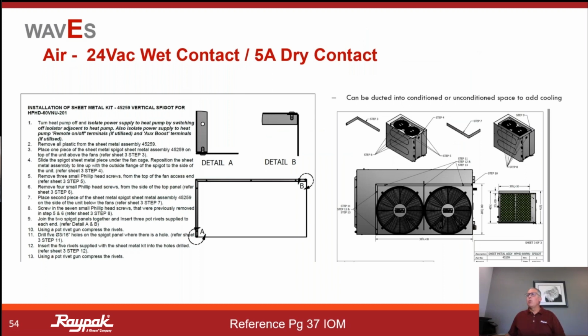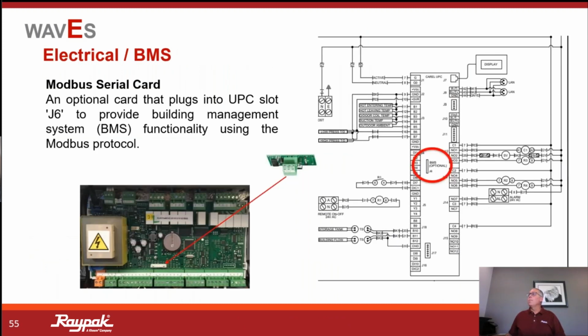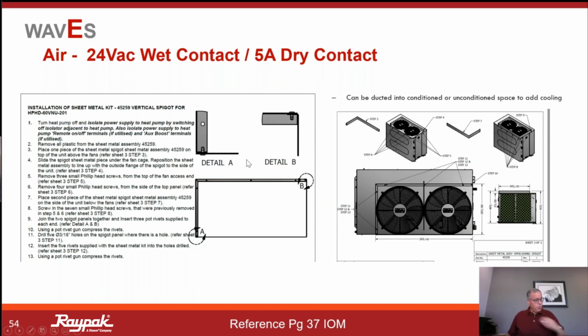Again, just going back to those terminals, I think I'm going to remove this slide, slide 54, since I talk about it in the electrical section. If we're using those ducting kits, I showed you on the electrical slide where that 24 volt wet contact was and that 5 amp dry contact was. So again, just make note, we can talk about if we're bringing on an ancillary fan to move that air to a different space.